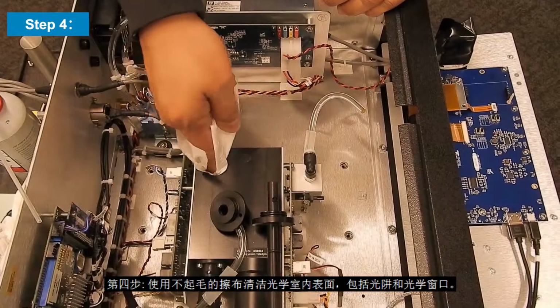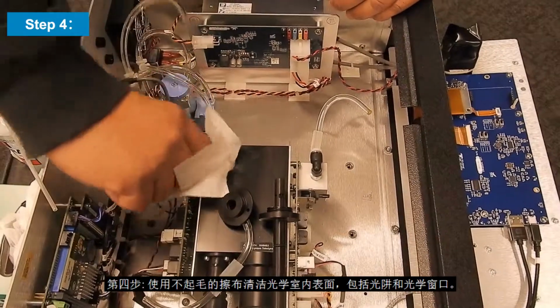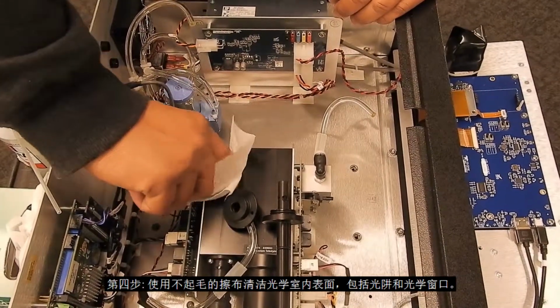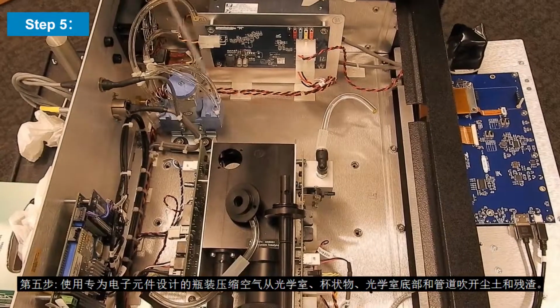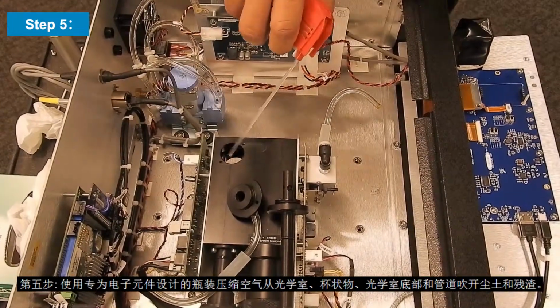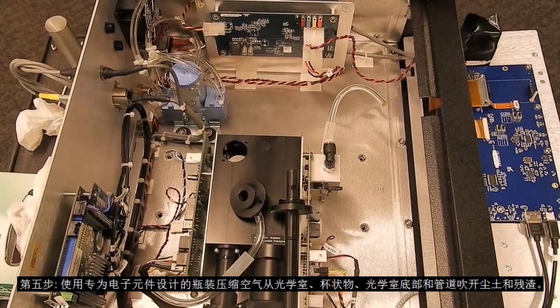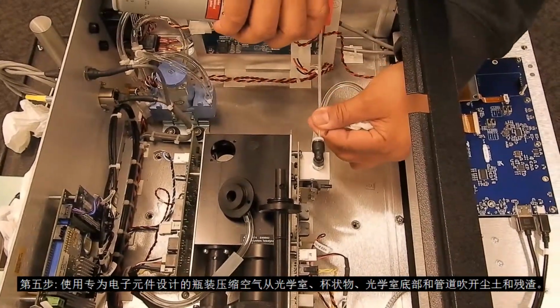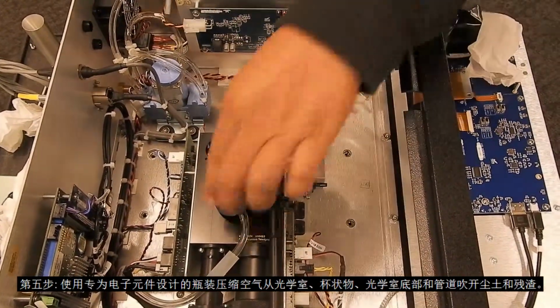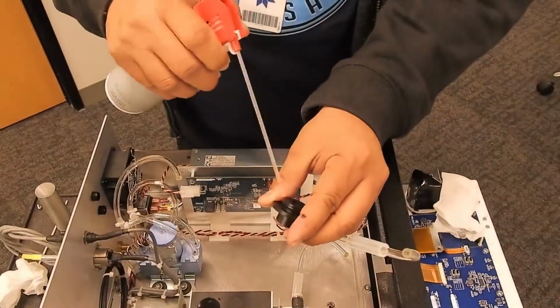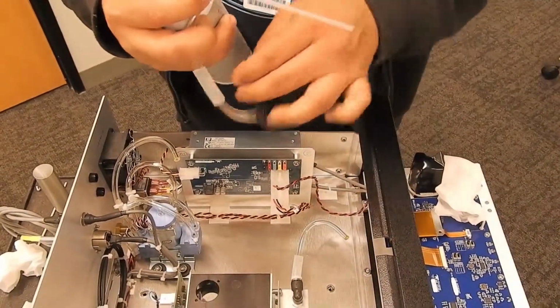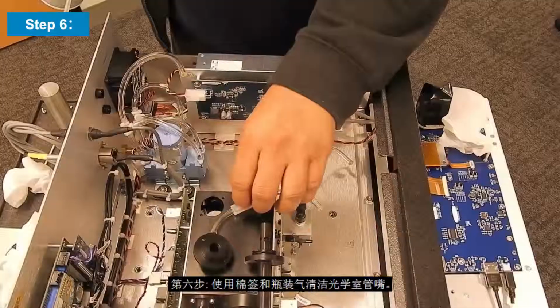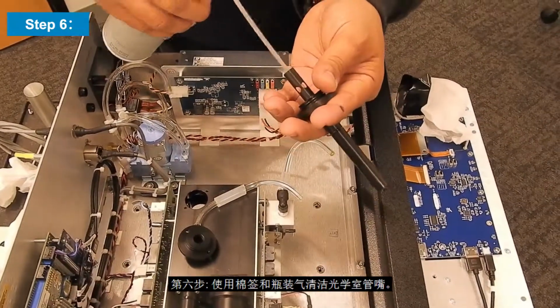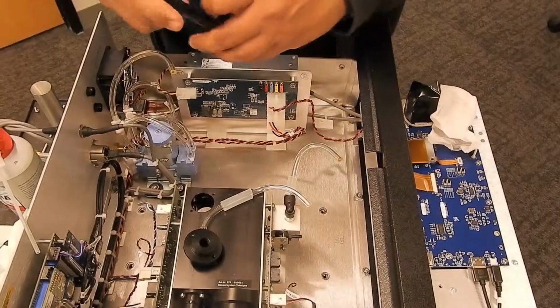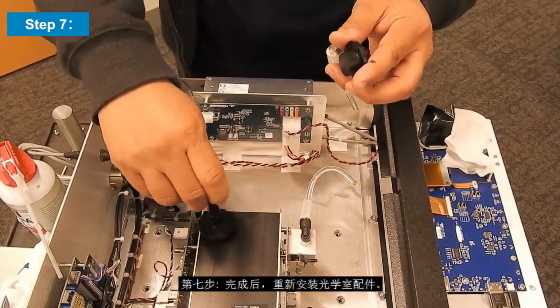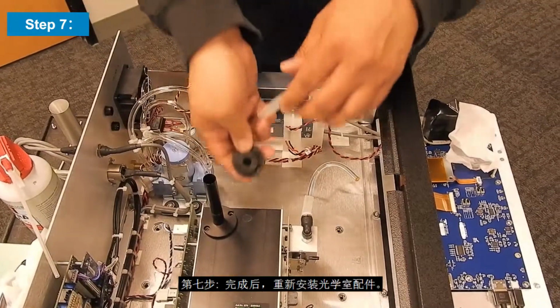Step 4. Clean the optics chamber interior surfaces, including the light traps and optical windows, with a lint-free cloth. Step 5. Use a can of compressed air made specifically for electronics to blow any dust or debris from the optics chamber, cup, bottom of the optics chamber, and tubing. Step 6. Clean the optical cell nozzle using cotton swabs and canned air. Step 7. When finished, reassemble optics chamber components.